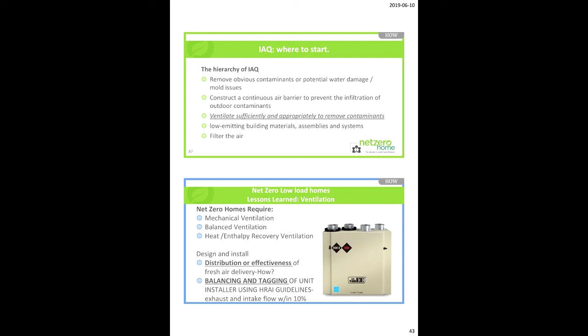HRV or ERV? How many of you are using ERVs? Sort of cool, isn't it? Eight years ago, I Googled ERVs and it told me I couldn't install them north of the Mason-Dixon line. ERVs typically will only be used in warm climates. Some manufacturers will go, oh, you can't do that. Like, the core's going to freeze up and the door's going to shut on you all winter. You're not going to get fresh air. Well, just wait a minute.